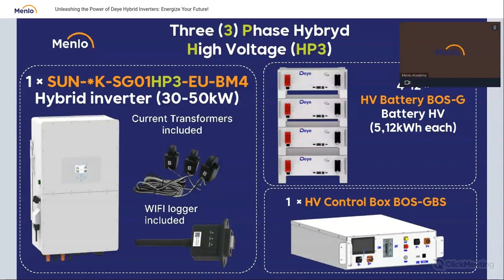It means that you can connect up to 222 kilowatt hours in one single 50 kilowatt installation without a complicated system, just with a typical hybrid inverter from Deye. No one else gives you that big a hybrid inverter. And the battery's power, next thing, for inverters up to 20 kilowatts, the maximum discharge power has 37 amps.